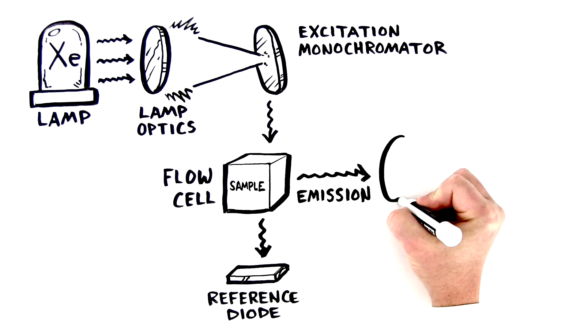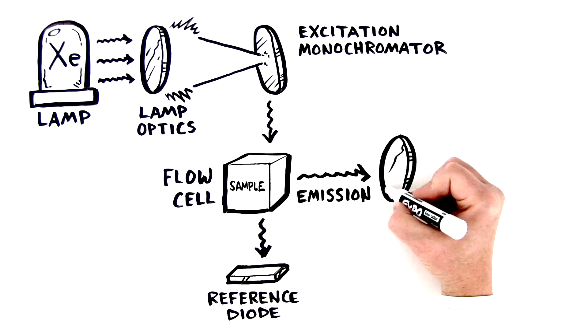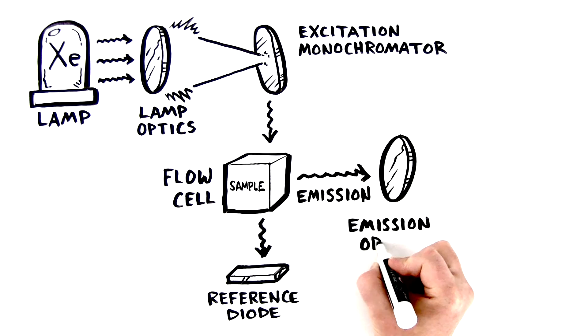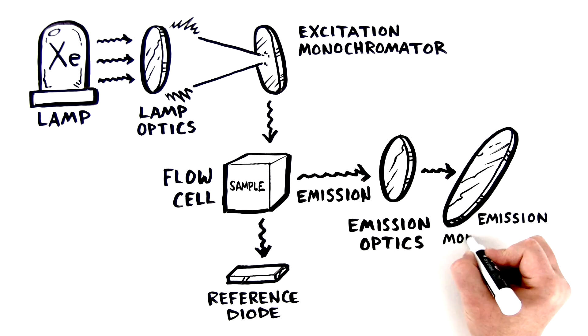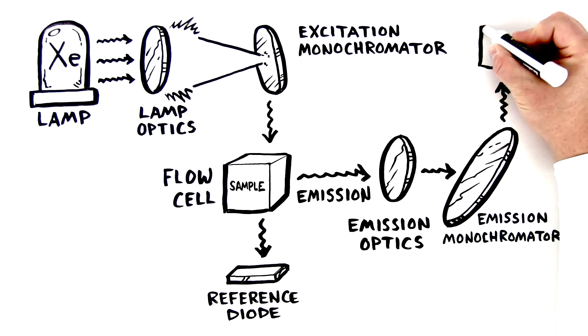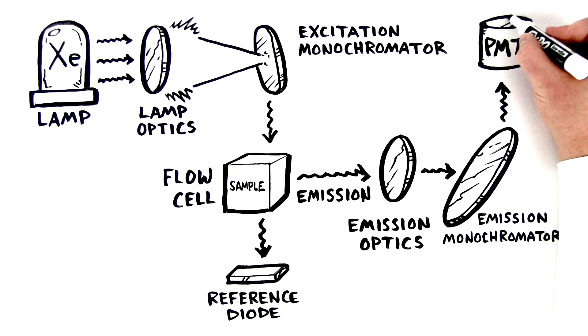Perpendicular to the excitation light beam, the emitted light is focused and filtered with emission optics. With an emission monochrometer, a specific emission wavelength can be selected. Light of this selected emission wavelength is then detected by one or two photomultiplier tubes, PMT.